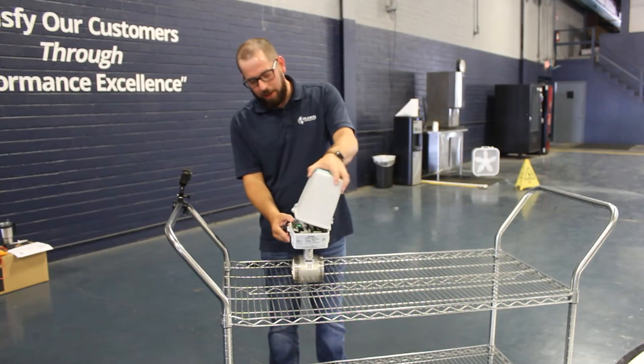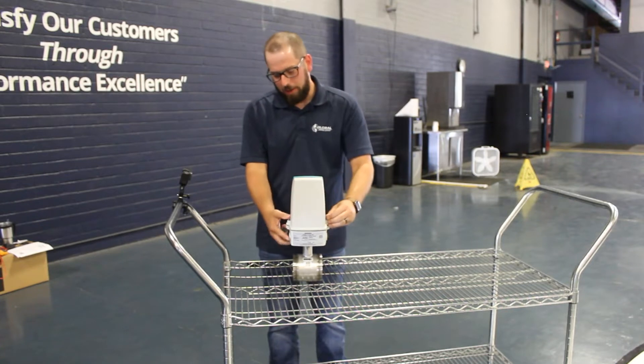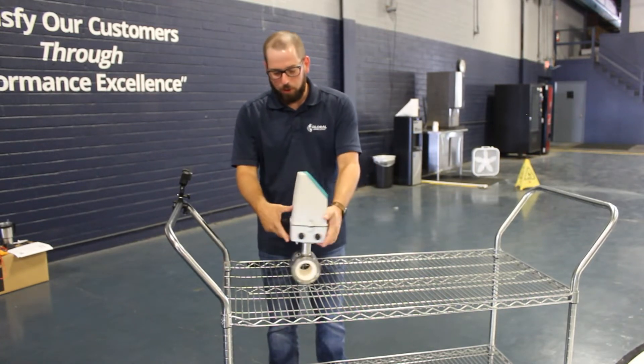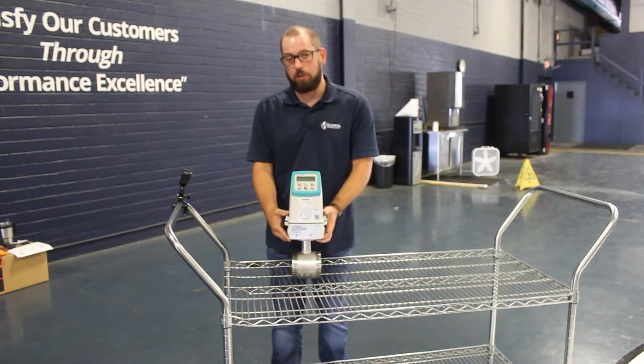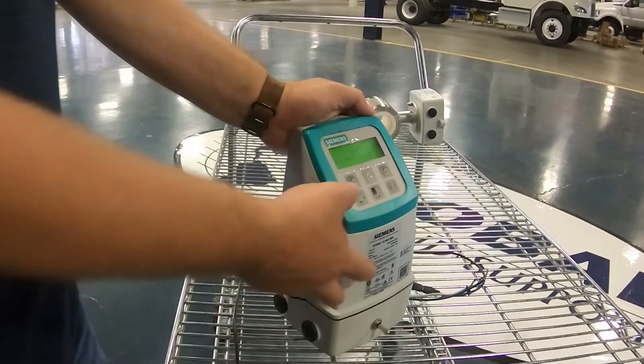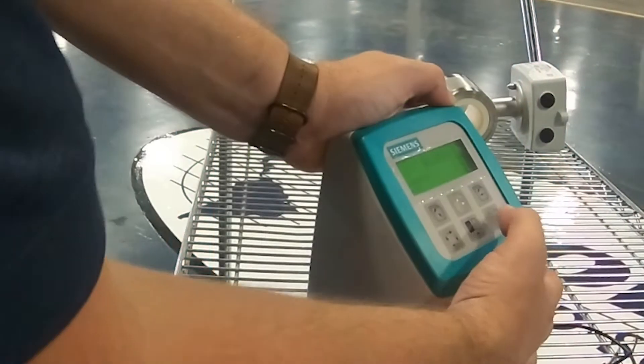The MAG 5000 head goes in here and then it's screwed down. This is what the fully assembled flow meter should look like. To unlock the system, hit this button and the password is 0000. Hit that button and now we're in the setup modes.